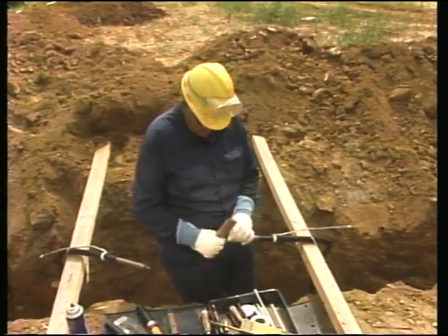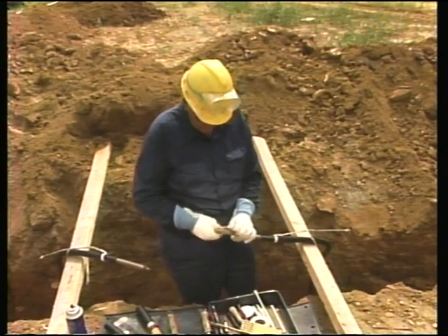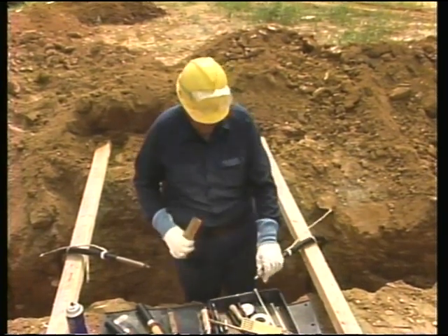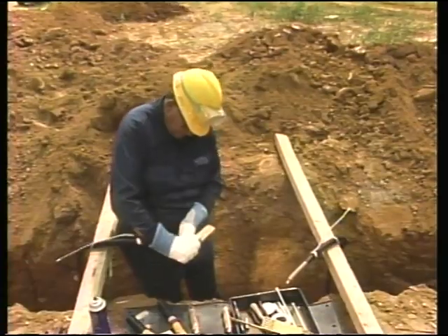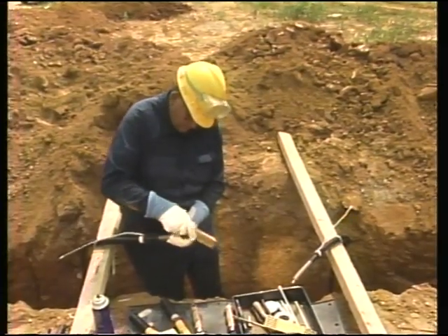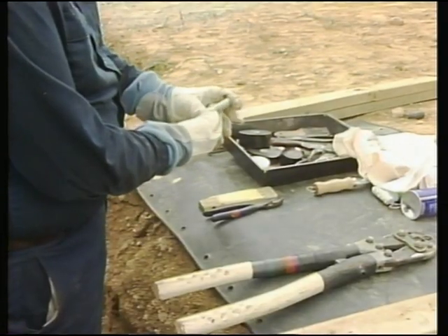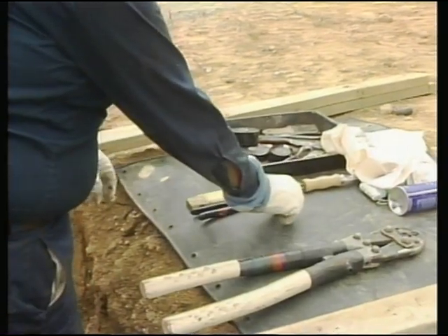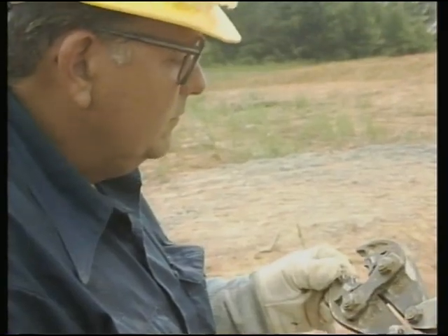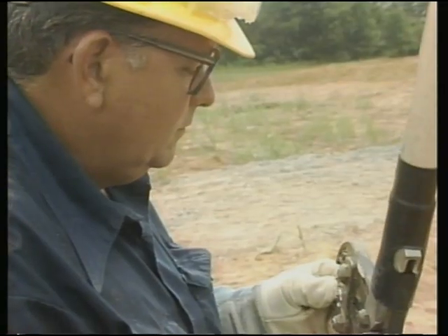It's important to remember that the cable splicing you'll be seeing here is unique to this situation and is only intended to be an example. Be sure to pay close attention to the instructions for your splice. The workman begins by cleaning the conductor with a wire brush. This helps to ensure good electrical contact between the conductor and the connector. He then checks his connector to see what type of die he should have in the press. Then he'll check the dies in the press to see that they're correct for the job.